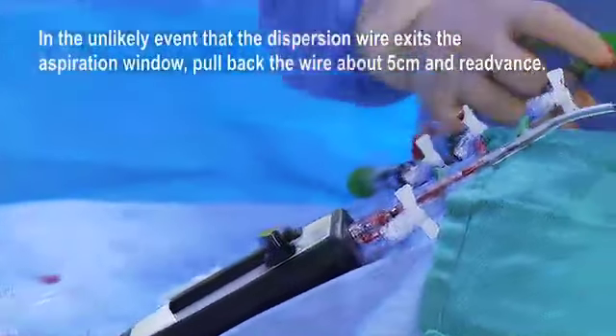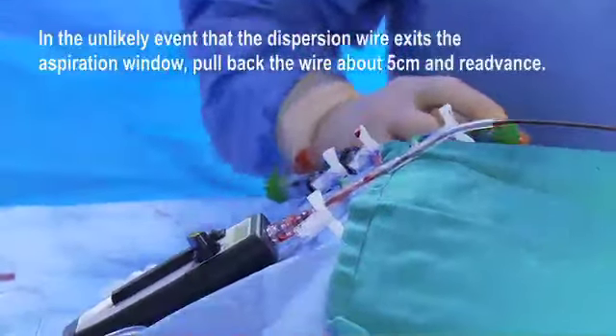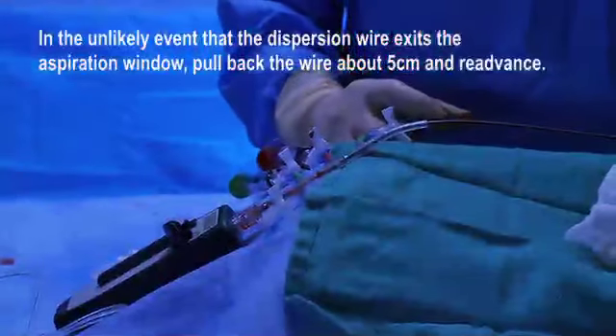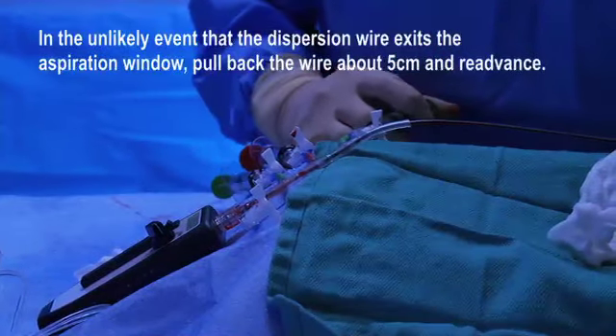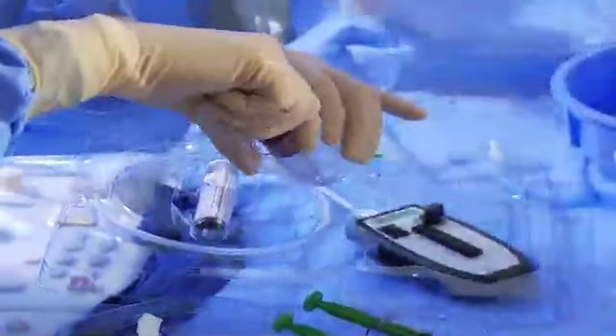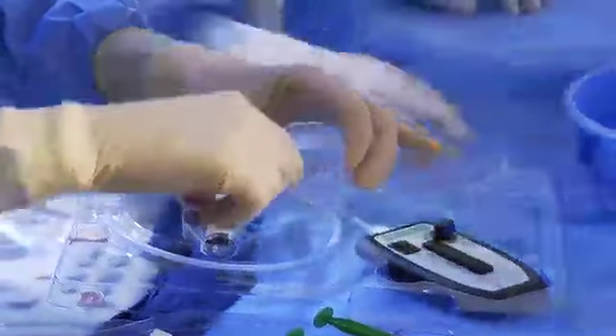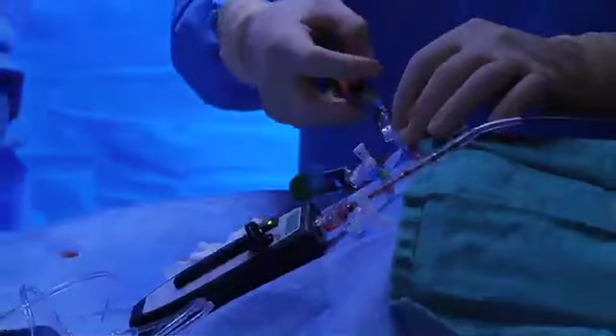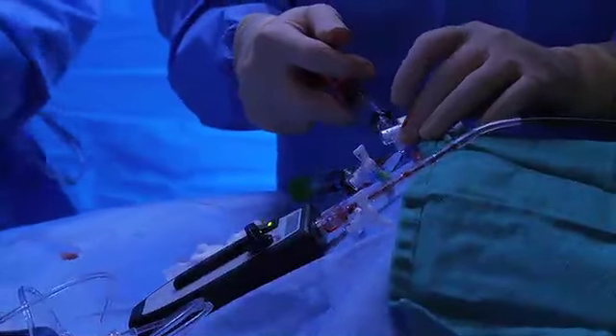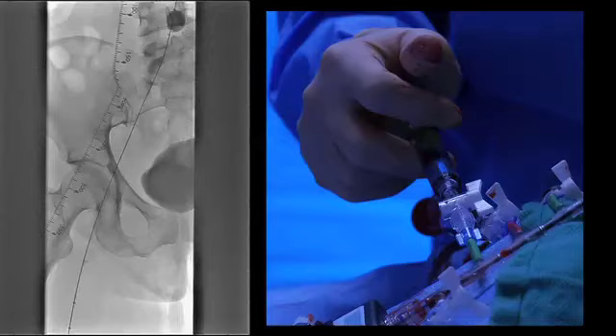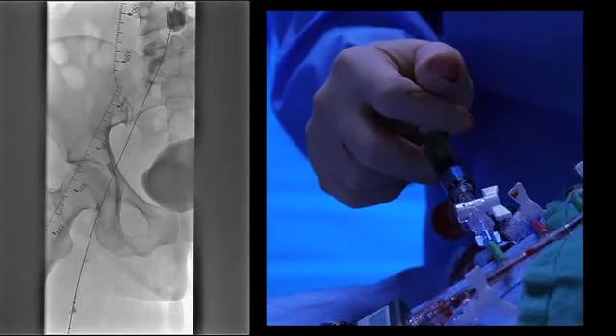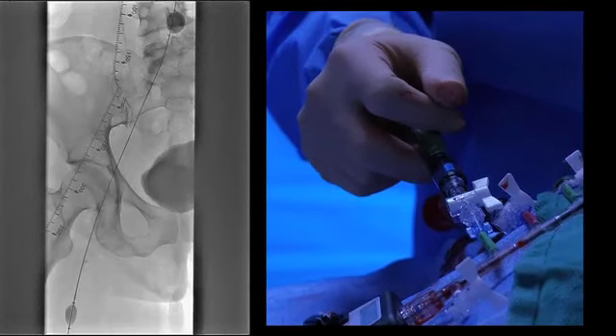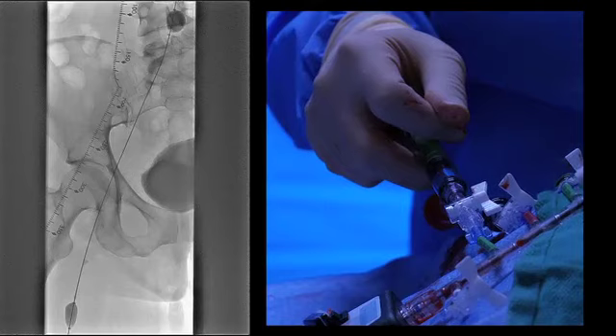In the unlikely event that the dispersion wire exits the aspiration window, pull back the wire about 5 centimeters and re-advance. Fill the 10 cc infusion syringe with the physician-specified fluid dose and dilute if necessary by filling to the 10 cc mark and attach the syringe to the infusion port on the catheter. For the antegrade approach, inflate the proximal balloon under fluoroscopy following the technique as described previously.